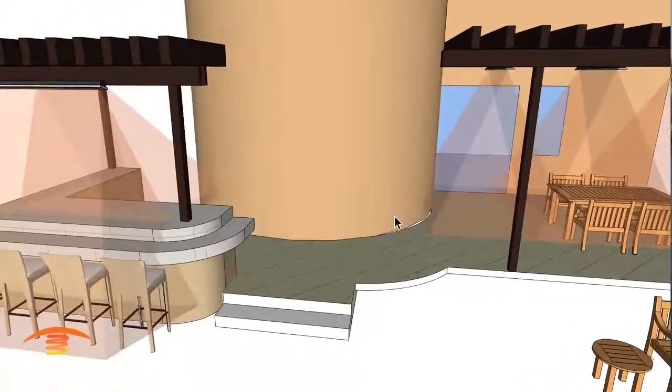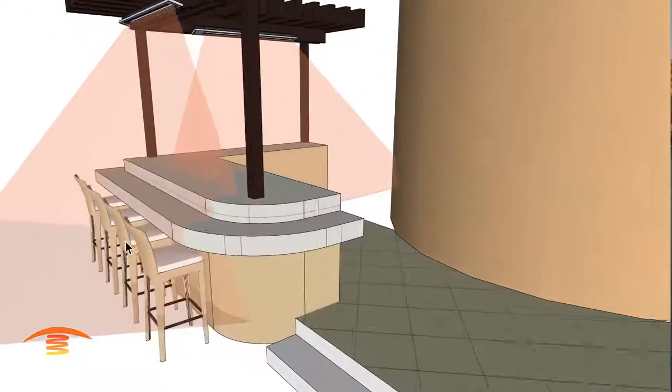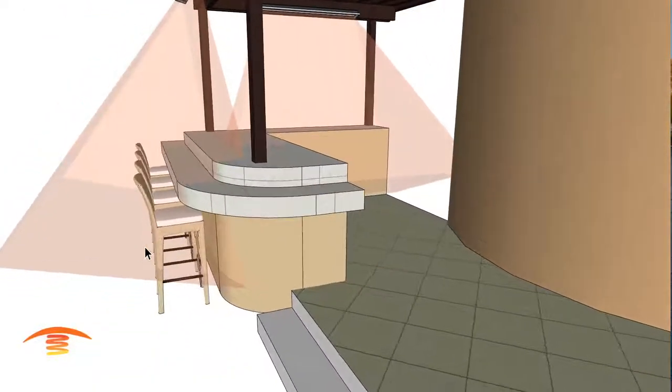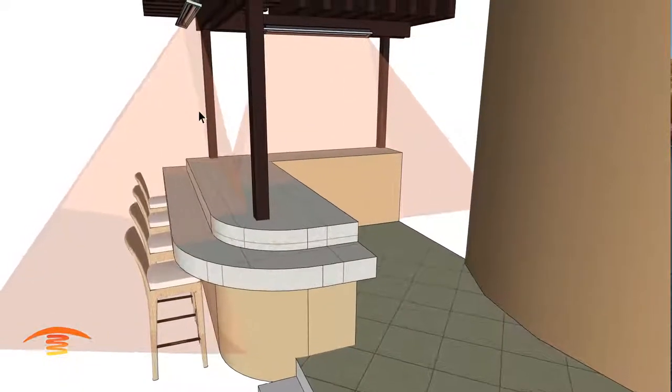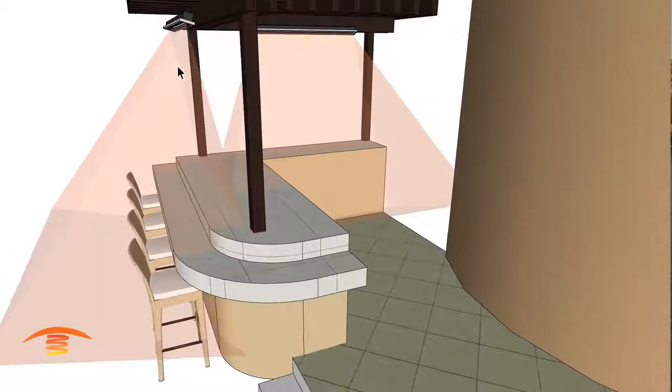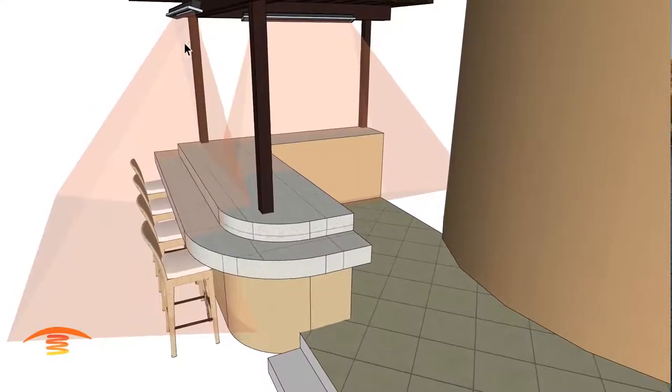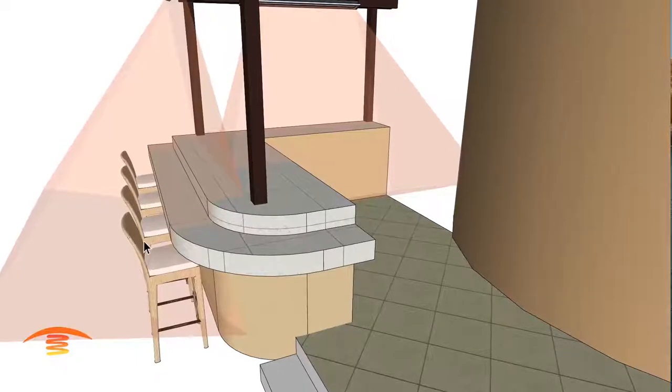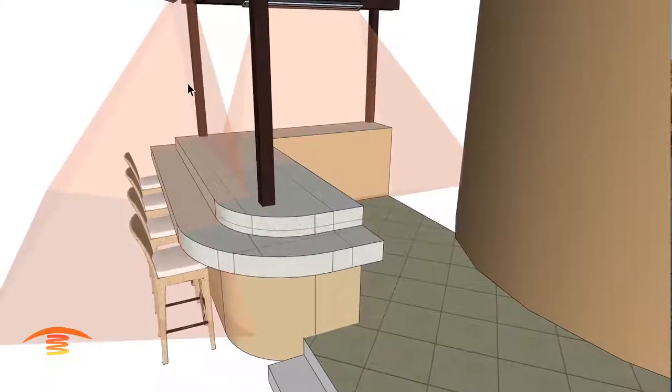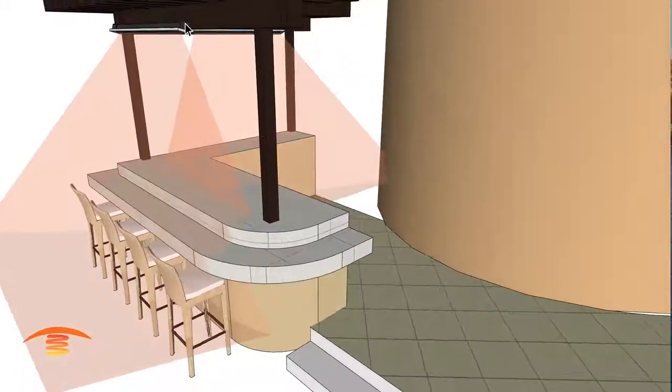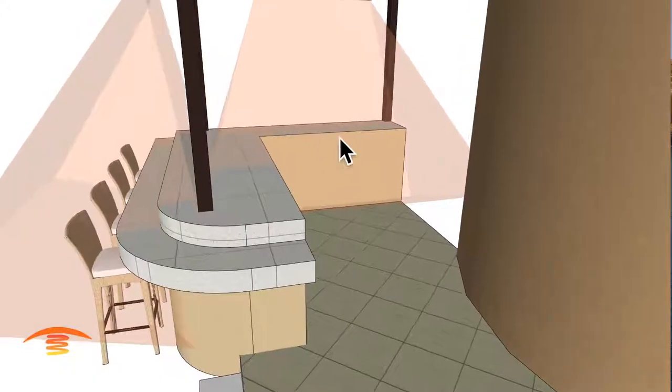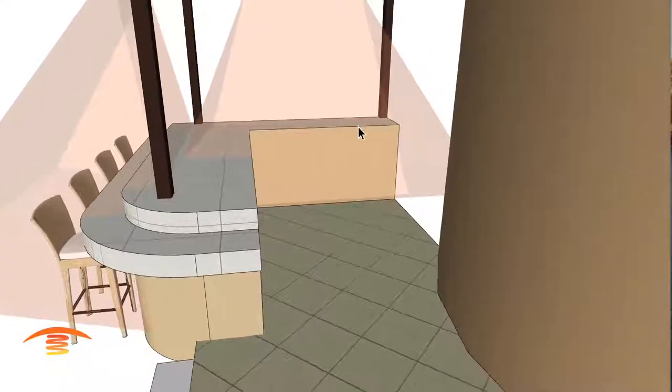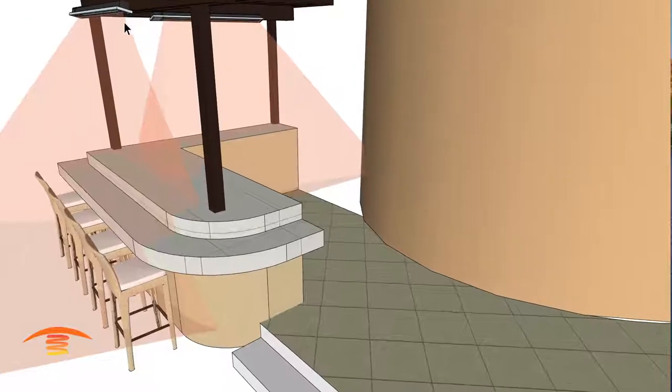And now, over here, I know the customer just was inquiring about this, so possibly nothing will go over here. But we could either put a 3,000 or 4,000 watt here. If you put a 4,000 watt here, it might be a little bit too hot in some instances, so you might want to have a control system on there. And, like a good salesman I am, I'm going to throw this heater over here for the guy that's doing the barbecue cooking.